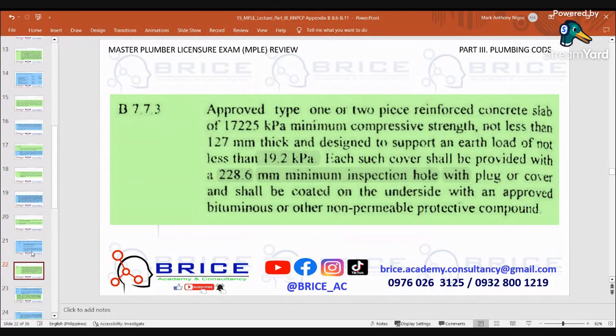Approved type of one or two piece reinforced concrete slab of 17,225 kilopascal minimum compressive strength, not less than 127 mm thick and designed to support an earth load of not less than 19.2 kilopascal. Each such cover shall be provided with a 228.6 mm minimum inspection hole with plug or cover, and shall be coated on the underside with approved bituminous or other non-permeable protective compound.